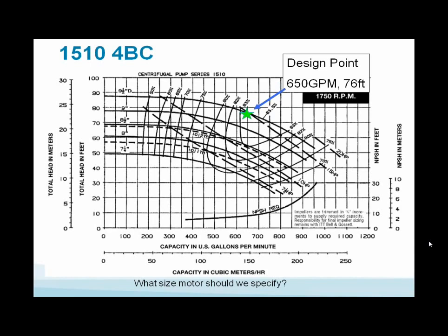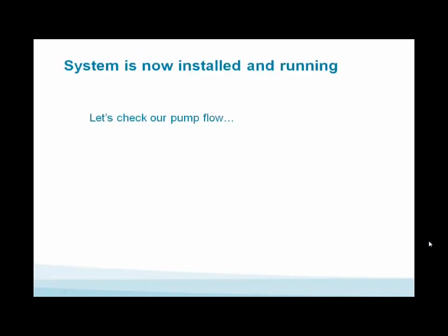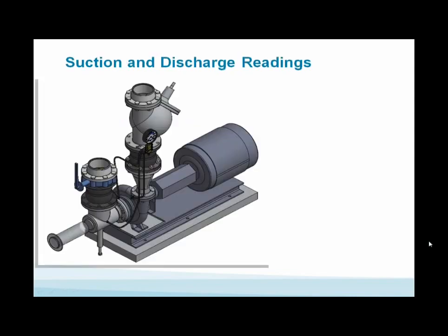I think I'd put a 20 horsepower to be non-overloading. So the system is now installed and running. Let's check out the pump flow. Let's see what really happened.